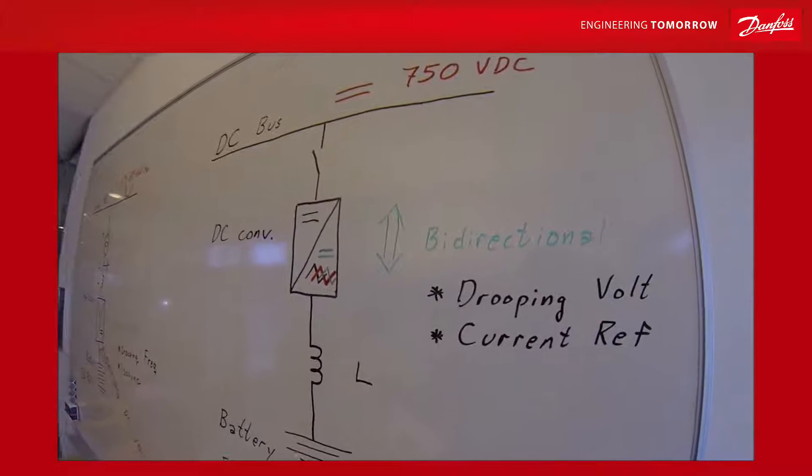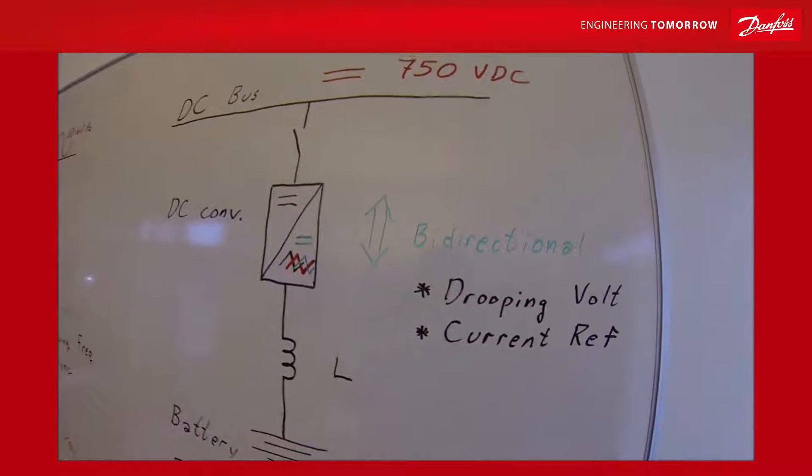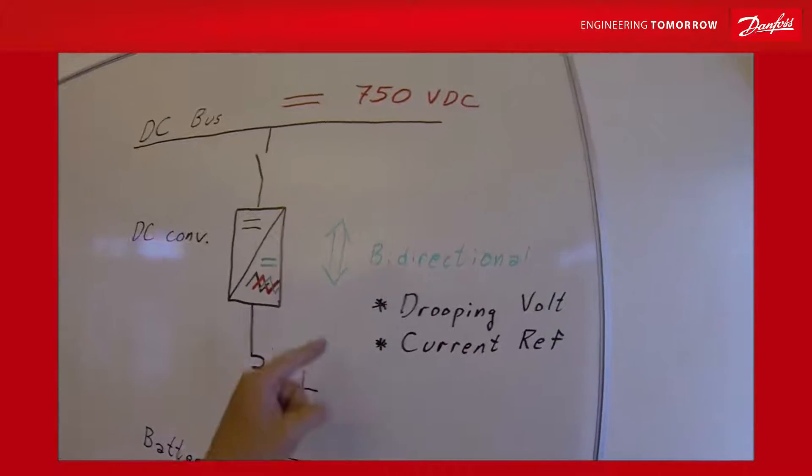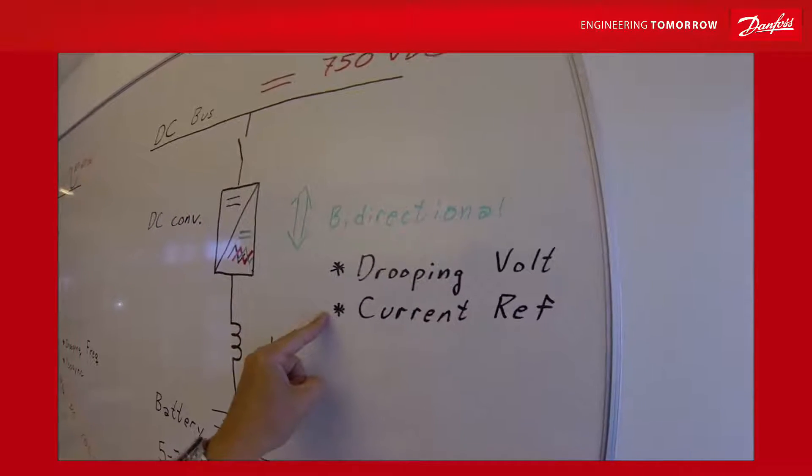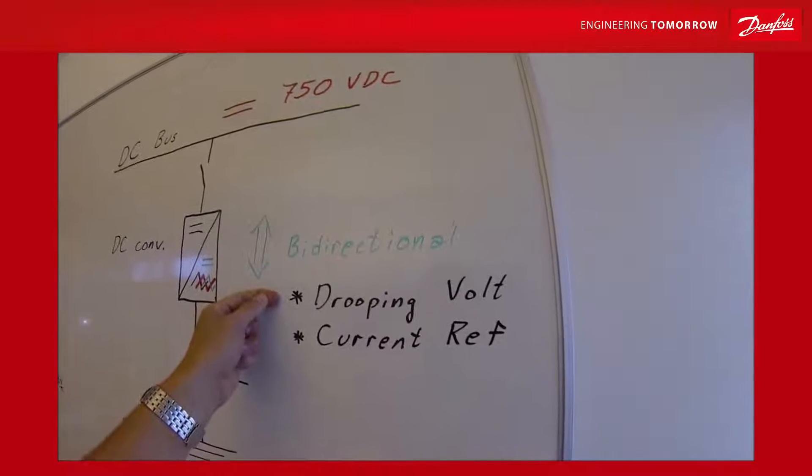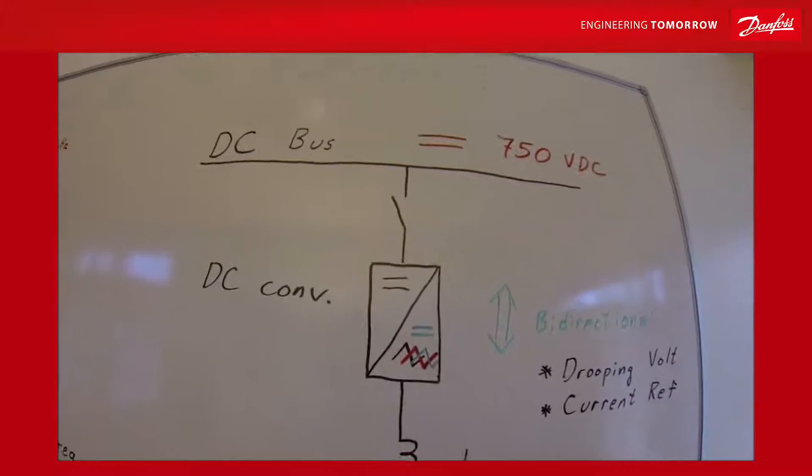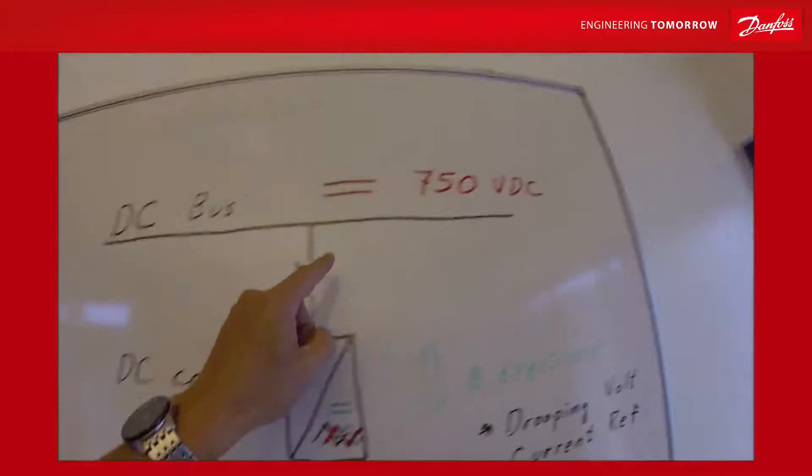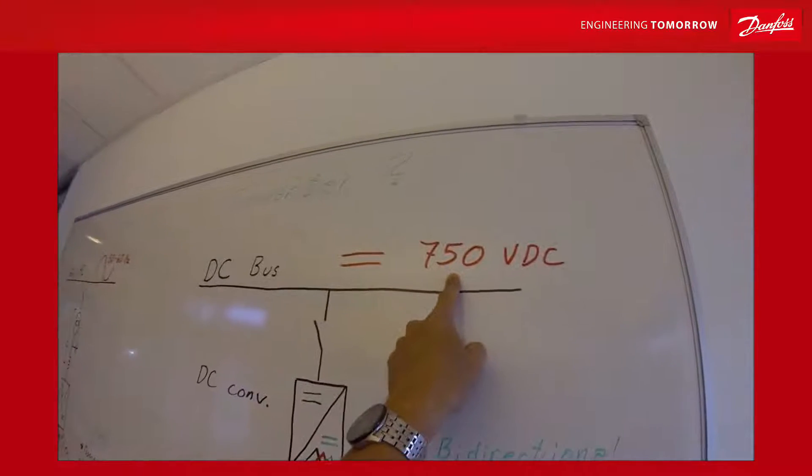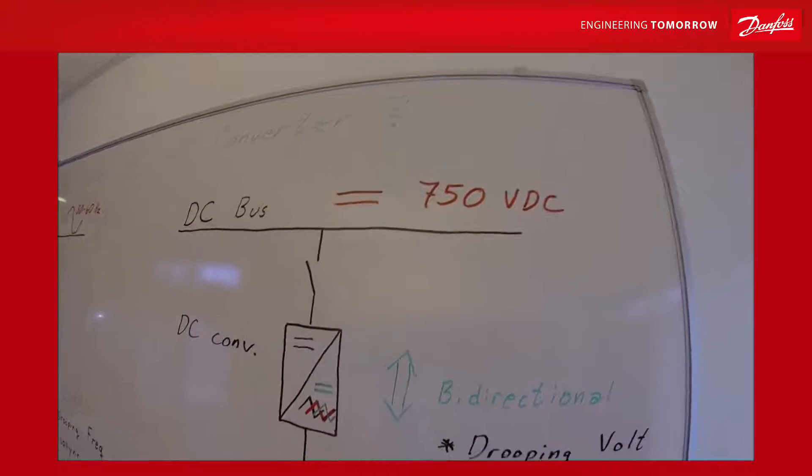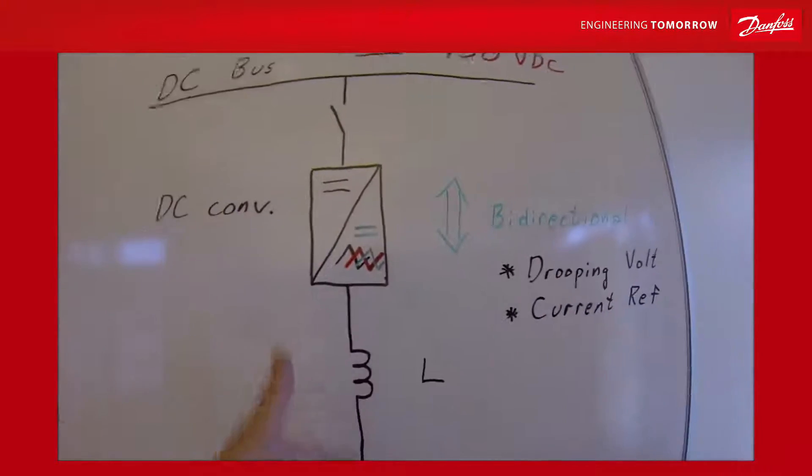Well actually from the operator side it's quite easy. There are two ways of controlling it. You can control it in drooping voltage. This is just like active front ends do, that is basically that you aim for the same voltage as the common DC bus and then you have some drooping as function of the load.